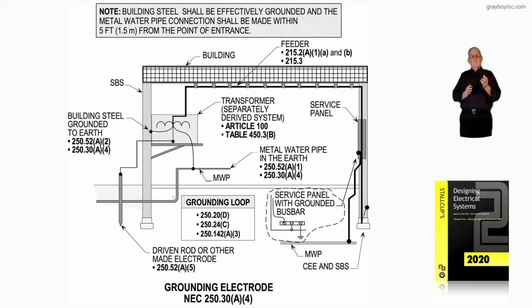And then if you couldn't get to the steel, you couldn't get to the water pipe system, and we're just saying if, then you could hit a driven rod, but the driven rod is usually bonded back into the grounding electrode system in accordance with 250.50. So under these conditions, then we're complying with 250.52(A)(2) and 250.30(A)(4) of the NEC.